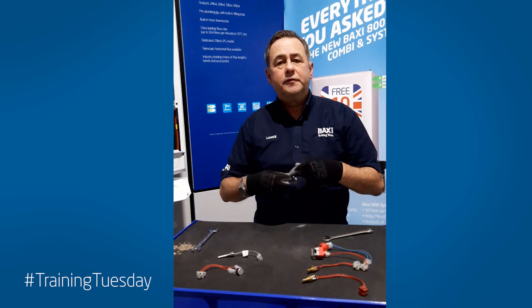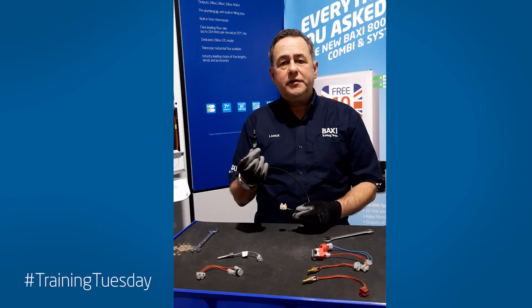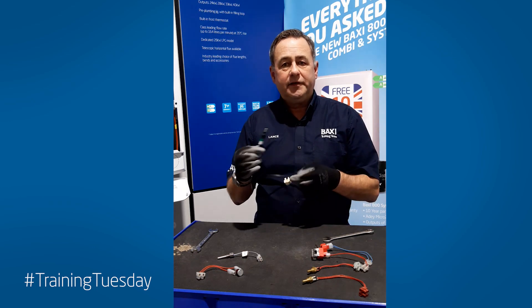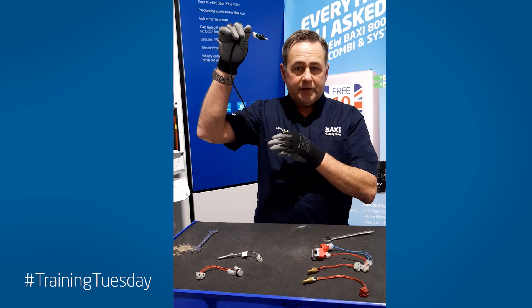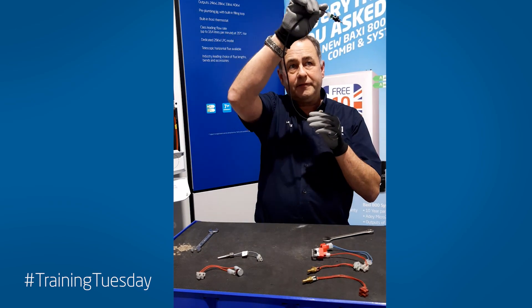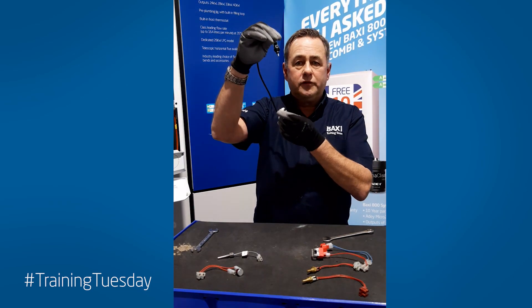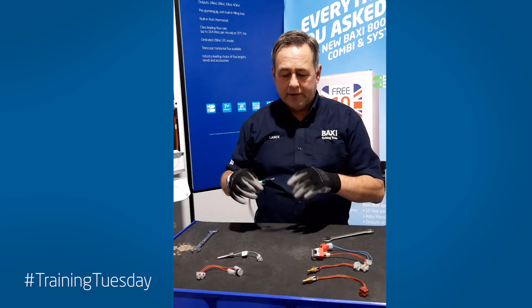This one is out of the stainless steel Giannoni heat exchangers. This one is used to measure the temperature of combustion. It's used like an overheat stat but it is actually a thermistor — we call it the flue thermistor. It sits at the top of the heat exchanger, either on the right or the left hand side of the flue. Very easy to get out, a simple quarter turn and retract it from the heat exchanger. Obviously if it's in combustion, it's a dry pocket.